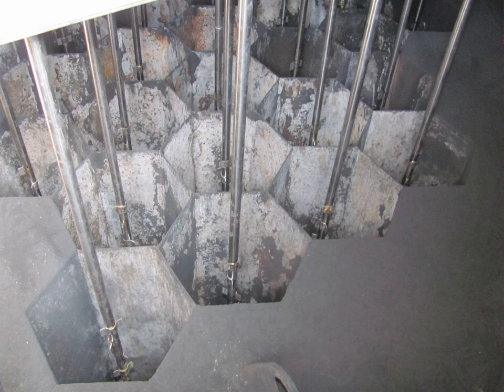Sulfuric acid vapor (SO3) enhances the effects of water vapor on surface conduction. It is physically adsorbed within the layer of moisture on the particle surfaces. The effects of relatively small amounts of acid vapor can be seen in the figure below and to the right. The inherent resistivity of the sample at 300 degrees Fahrenheit (150 degrees Celsius) is 5 × 10^12 ohm-cm. An equilibrium concentration of just 1.9 ppm sulfuric acid vapor lowers that value to about 7 × 10^9 ohm-cm. Topic: Modern industrial electrostatic precipitators.